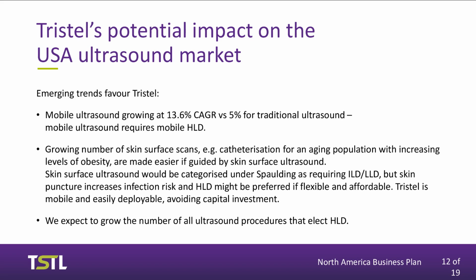But when that skin surface ultrasound transducer, which classically has been considered to be low risk, is in the proximity of a skin puncture site, all of a sudden that procedure becomes high risk. If it was affordable and available, I think most sonographers in the United States, as evidenced by lobbying that is very prominent and current at the moment, would prefer to use high-level disinfection. One of the key characteristics of our product is, as I've said, it's mobile, easily deployable, it never breaks down, and it doesn't require capital investment. So we do believe that the number of ultrasound procedures that require high-level disinfection in the United States over the next decade will increase as a direct result of the availability of our technology to the market. So to the next slide, please.